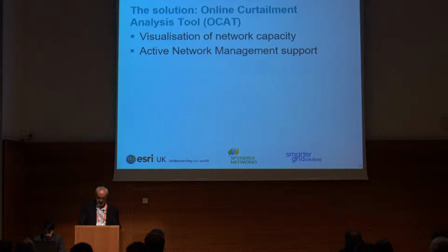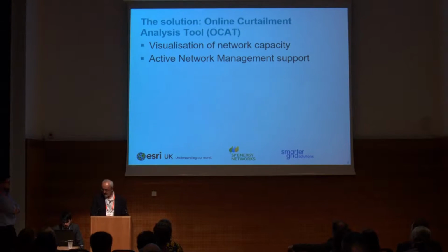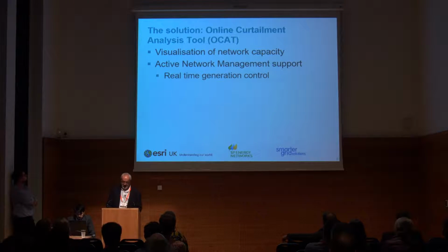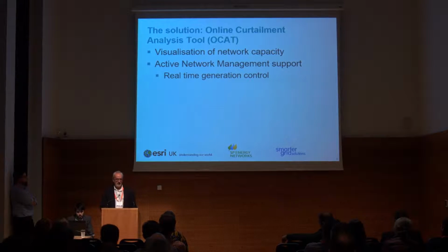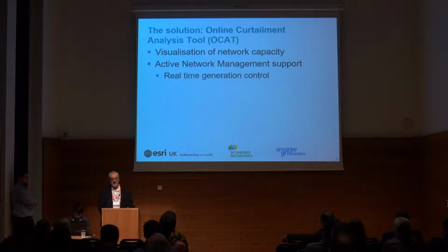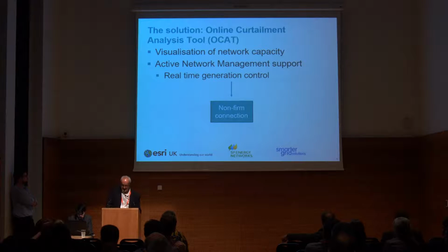We're also looking to provide up-to-date and accurate information on the network and provide enough information to enable customers to make an informed decision on the feasibility of an application. Active network management means taking some intervention to the generation point, no matter what the technology is. But predominantly at the moment we're working with wind and solar. All quotations to date have been what's called firm. That is, no action is taken. And the move forward now into the more active network, to move towards smarter grids, requires intervention.